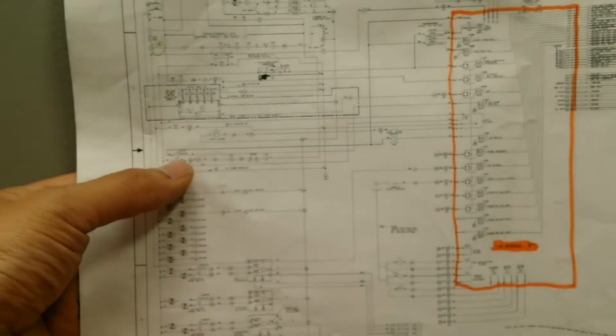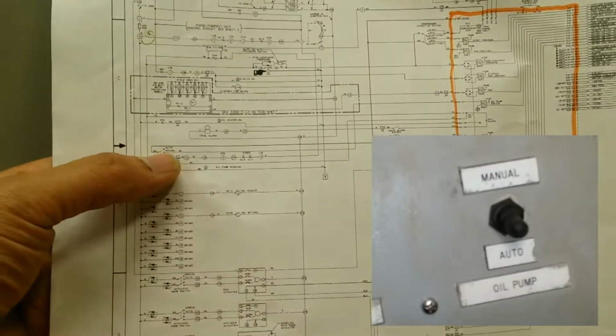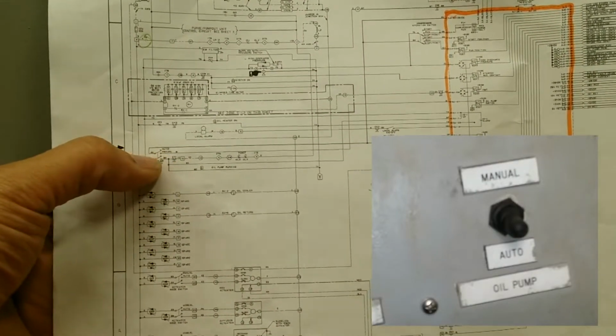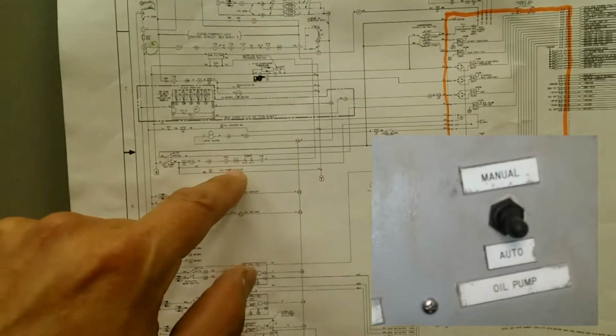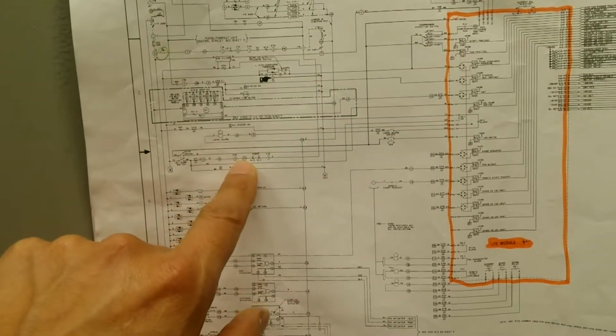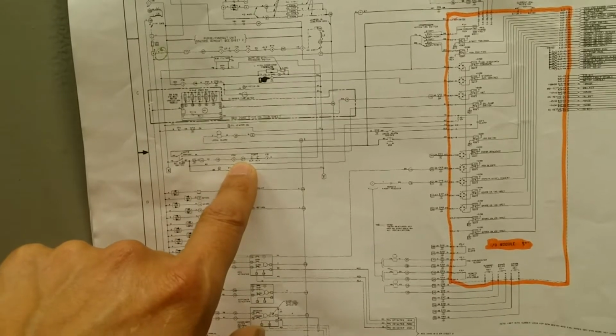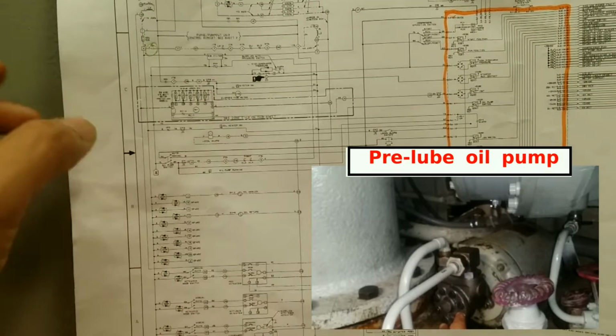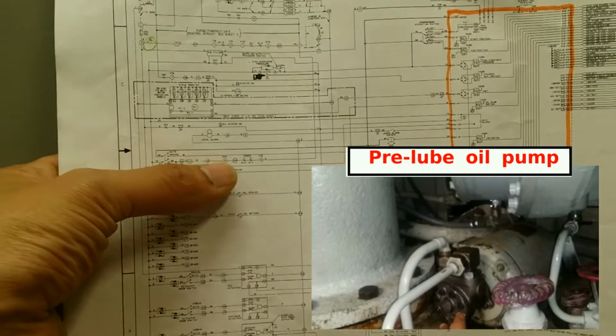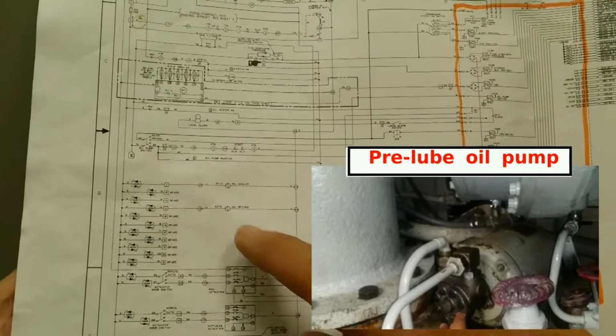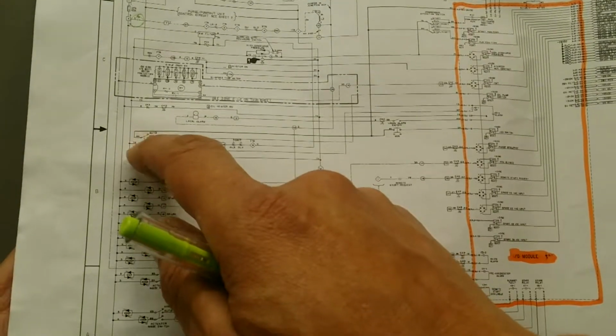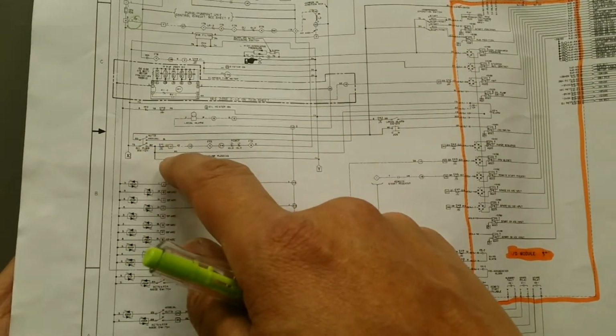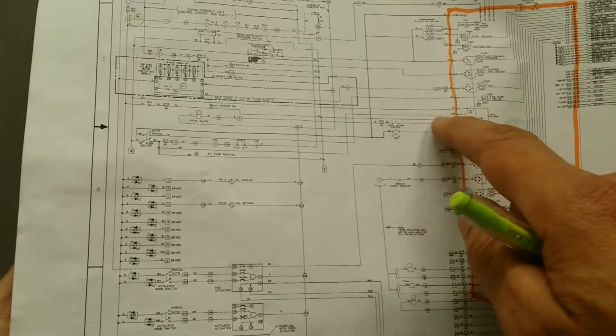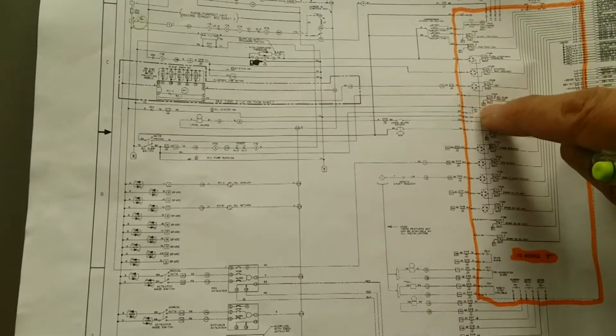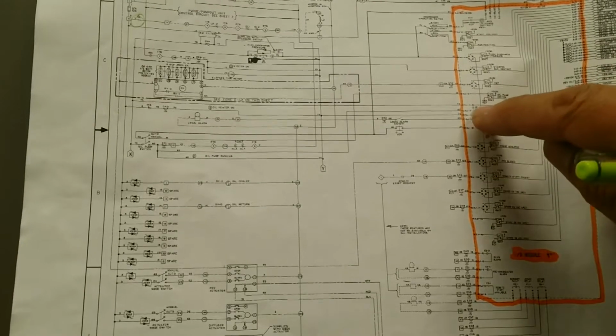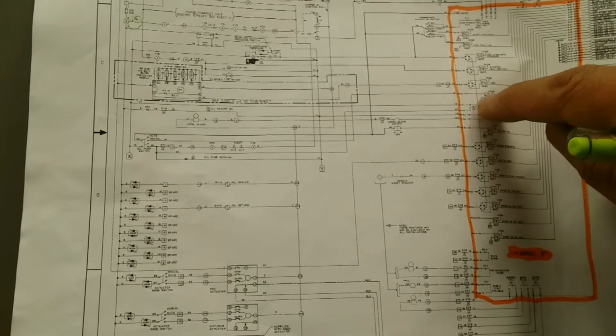Now, the 4th one over here, when you put it in auto, you're really disconnecting it. And when you put it in manual, you just put voltage to it straight, and you energize 3M. 3M is the contactor, in my case, that energizes the auxiliary pump. If I suspect that this auxiliary pump is not automatically coming on, the first thing I'll do is put it in manual, and then the pump comes on, and then I will investigate why it's not automatically coming on. When you put it in auto, since you are removing the power from it, now the only way for it to come on is if it's being fed from the microprocessor. This one is the input and output module via relay K2.